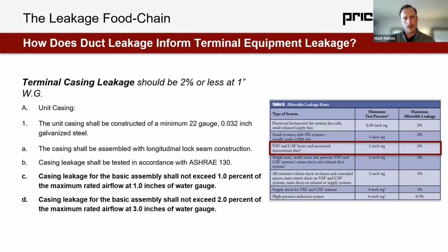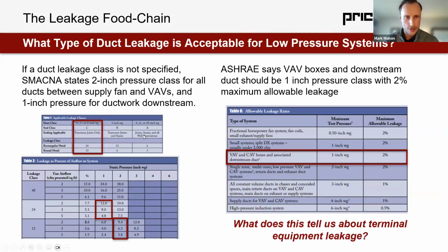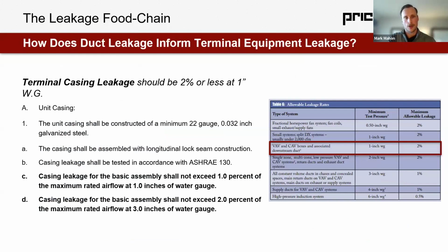And when we look at that, I'll go back to here, it's small, so I apologize for the small text, but seal class A is joints, seams, and wall penetrations. Most VAV boxes installed in California, even though we can meet the spec already, often have contractors seal the wall penetration. So where the inlet meets the inlet panel, the round meets the flat. They are sealing transverse joints, so they're sealing slip and drives between a single duct and a water coil, or the water coil downstream. And they're sealing box seams at times too, which is probably overkill, but that's often what we see in installs in California.